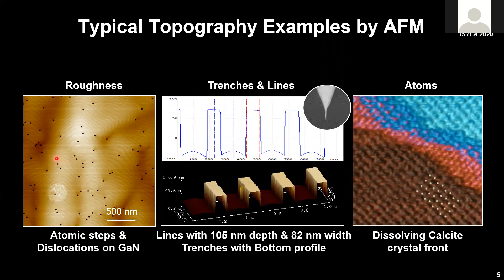On the left side there's a roughness example — a gallium nitride wafer that shows terraces as well as dislocations. We can clearly resolve both the terraces, which are very small steps, and the dislocations, which are small pits into the surface. We can extract dislocation densities. The middle shows a typical 3D measurement of trenches and lines for critical dimension metrology.